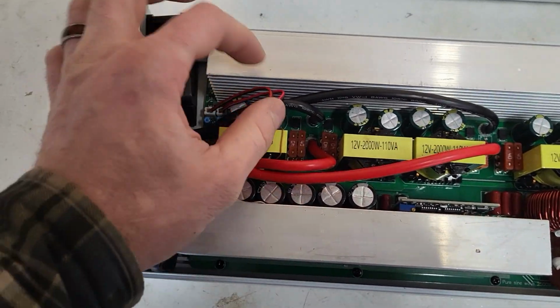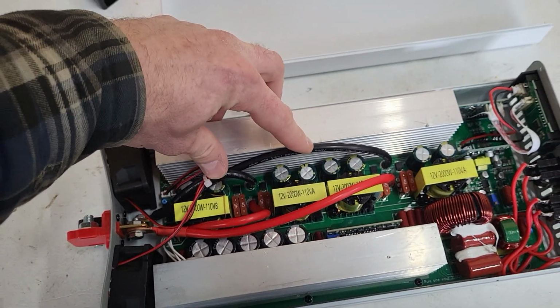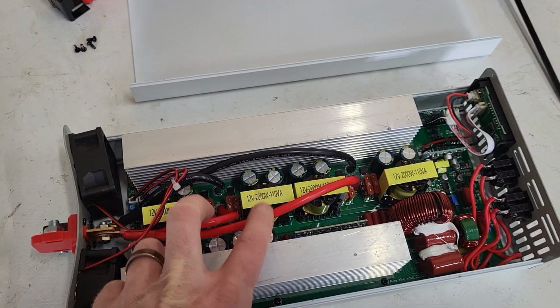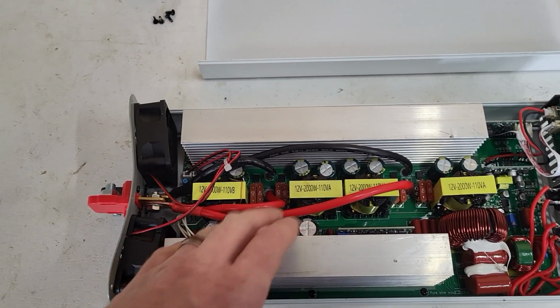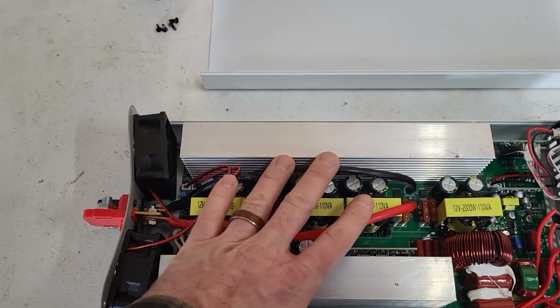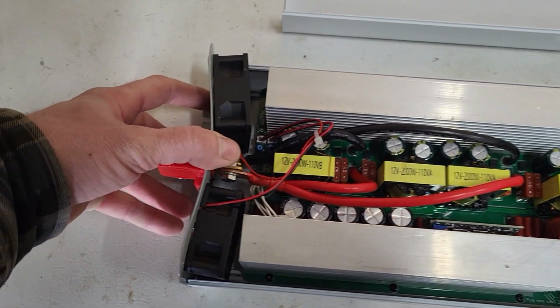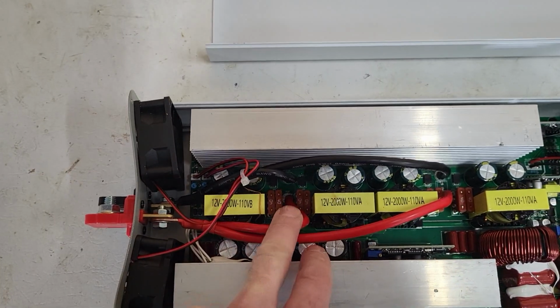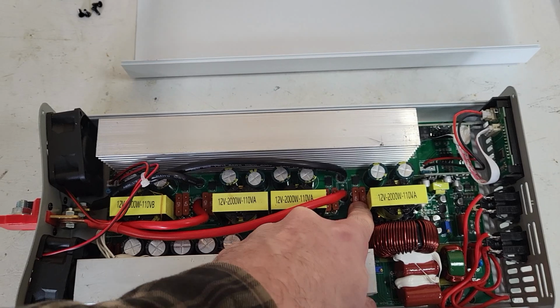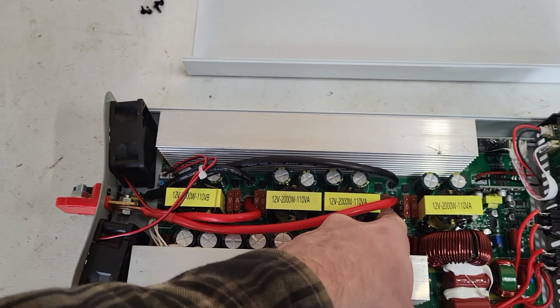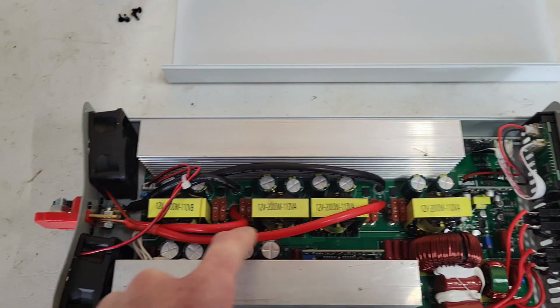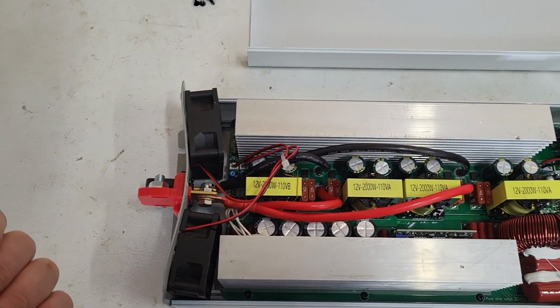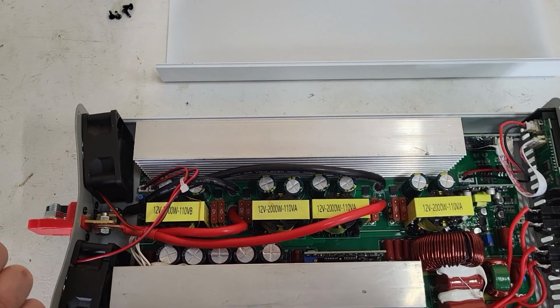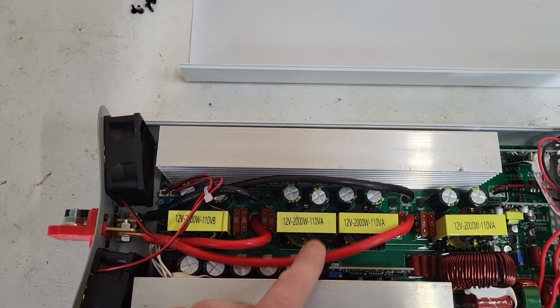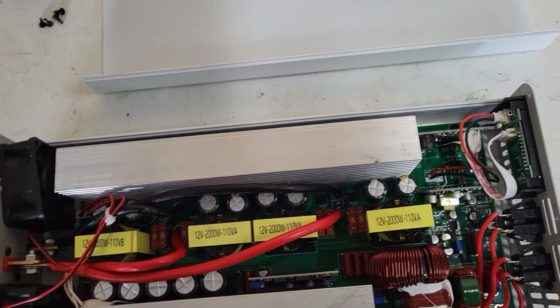Got some nice thicker wire, we got two rounds of 8 gauge, which is a little on the thin side for the inside, but they've got cooling fans running cold air, and that's probably how they get away with a smaller wire on the inside. Lots of fusing. Holy smokes, we got 80, what is that, 80, 160, 320 amps worth of fusing. That is a lot of fusing. This thing must be able to push some decent current if it's got that much fusing.